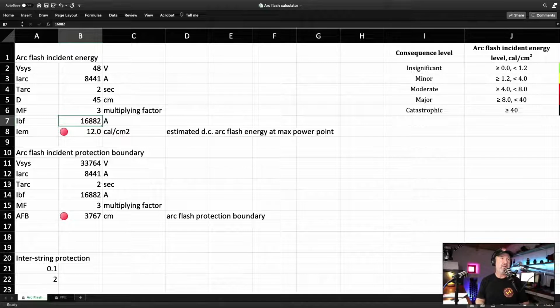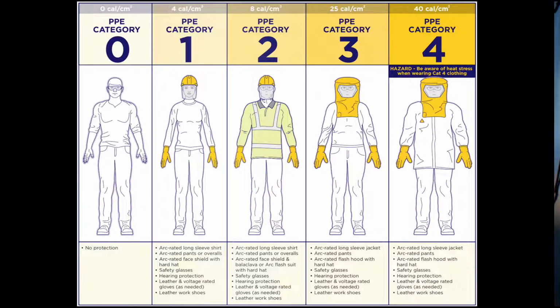If I bring up a PPE diagram, remember 12 cal per square centimetre, and what does that look like? 12 would be category 3: an arc rated long sleeve jacket, arc rated pants, arc rated flash hood with a hard hat, safety glasses, hearing protection, leather and voltage rated gloves, leather work shoes. Gee, just kitting yourself out is going to cost a lot, let alone how easy it will be to work in all that. And hopefully you don't live in a hot place. So that's a pretty serious level of PPE for that system.